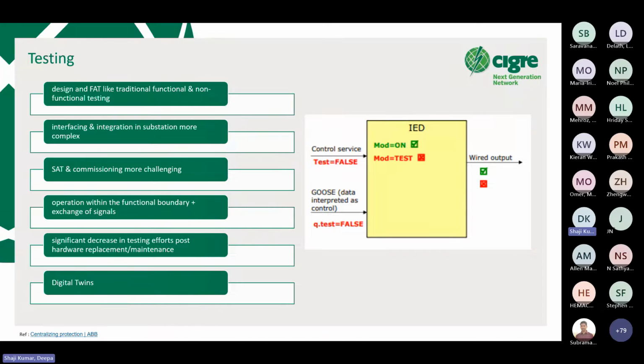61850 provides ample guidelines for entire quality processes, including recommendations for functional testing and requirements for conformance testing. These guidelines are independent from hardware and therefore applicable to protection and control functions and control systems with functionalities independent of hardware. For example, 61850 specifies requirements regarding engineering tool support based on use cases along the entire life cycle, and system-related function test principles, which had been added to parts like 10-3. Furthermore, there are additional 61850 series parts which provide requirements regarding system management during the life cycle of protection and control systems.